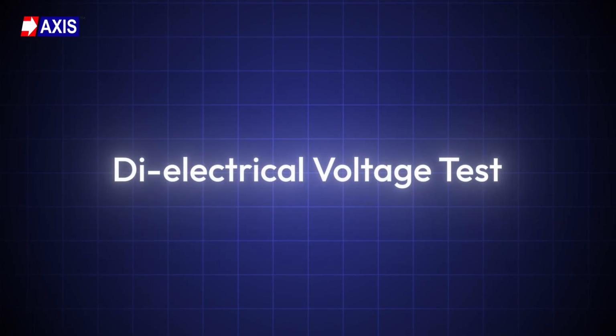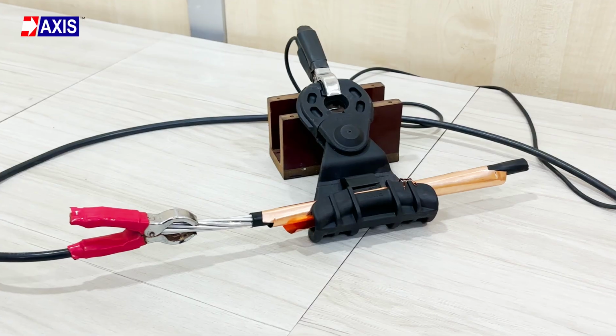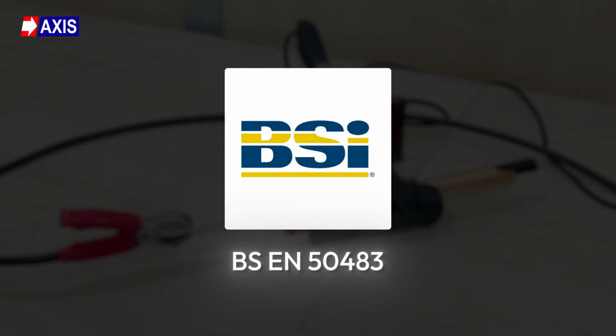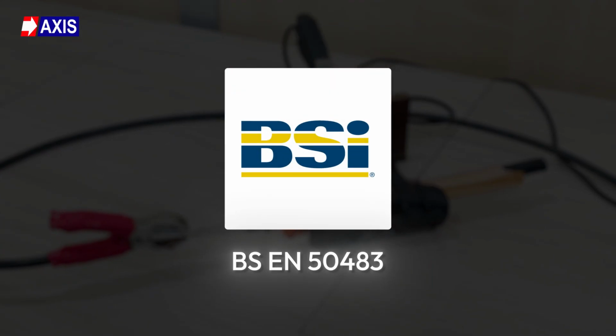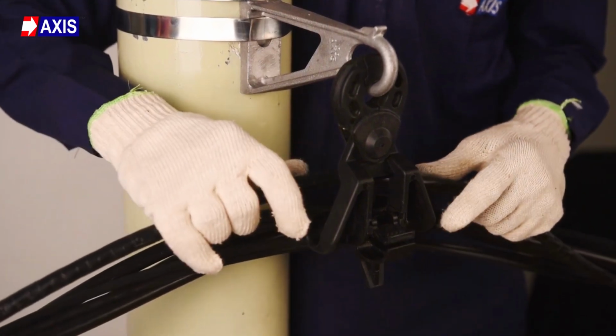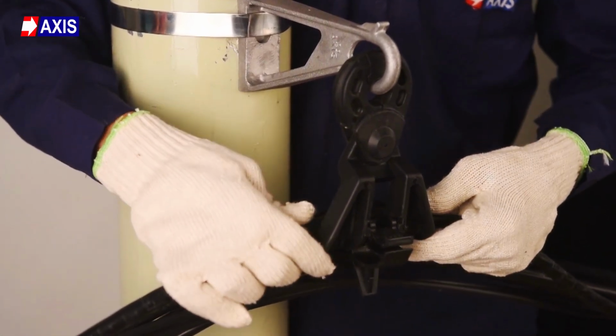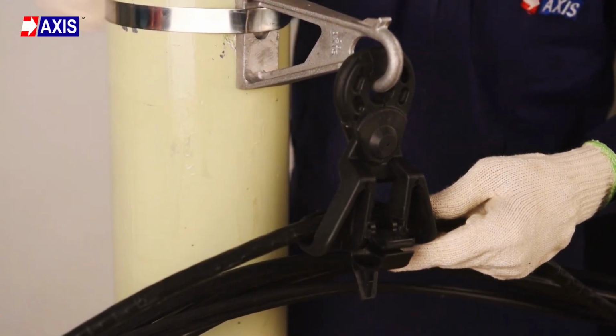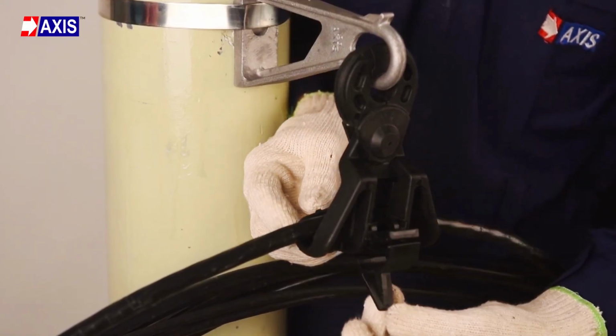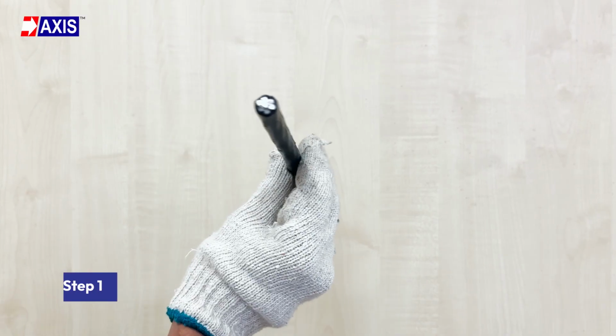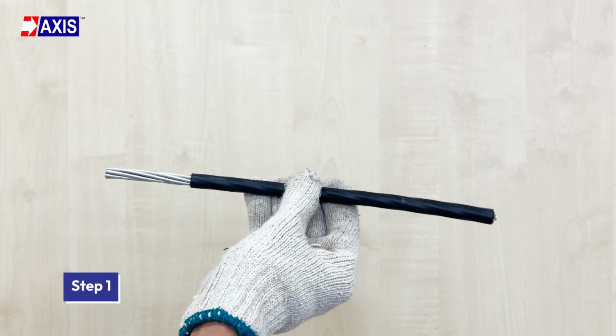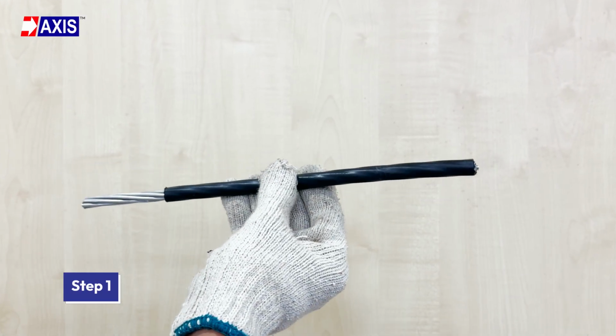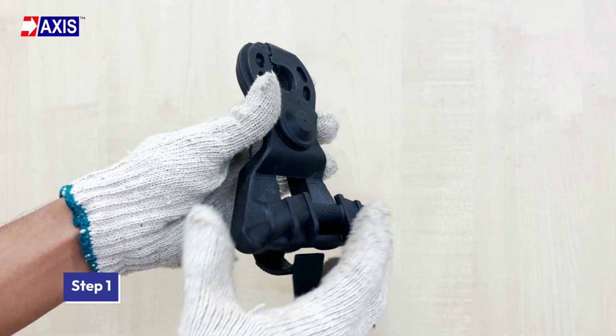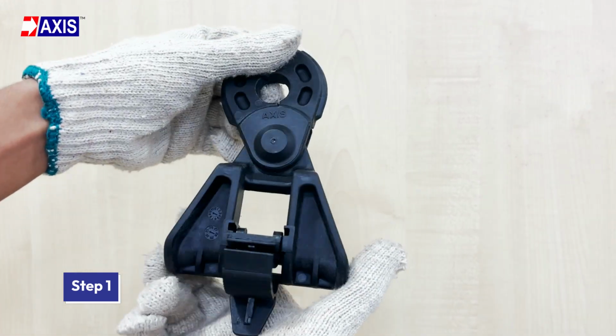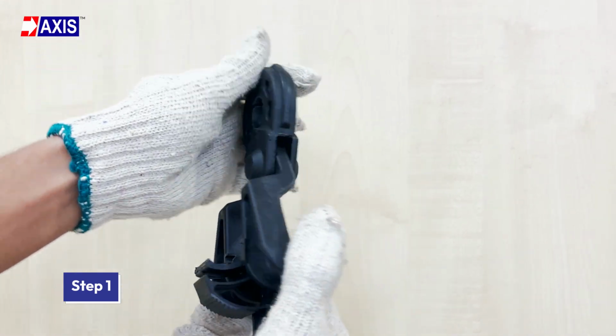Let's start with the dielectric voltage test. This test is performed as per BS EN 50483. Its goal is to verify that the suspension clamp keeps its insulation intact and does not break down electrically after mechanical or environmental stress. Step 1. Prepare the test sample of the insulated neutral messenger and the suspension clamp. Ensure the cable sheath and clamp surfaces are clean and dry before testing.